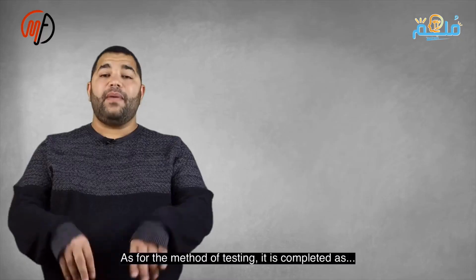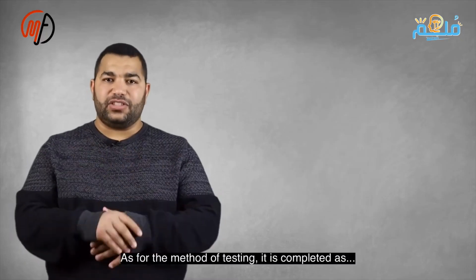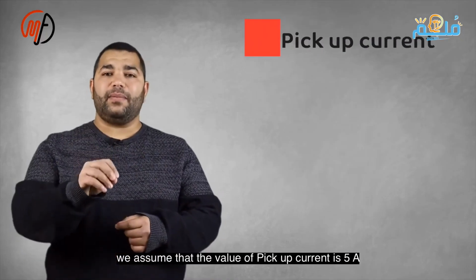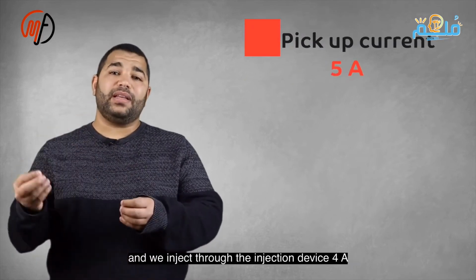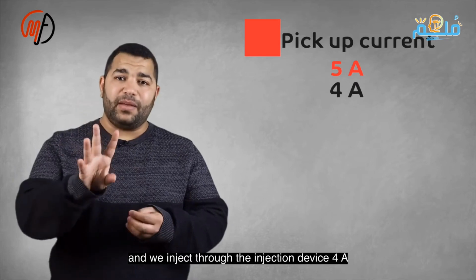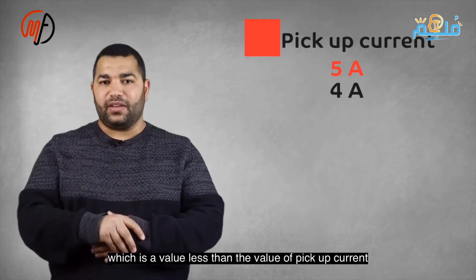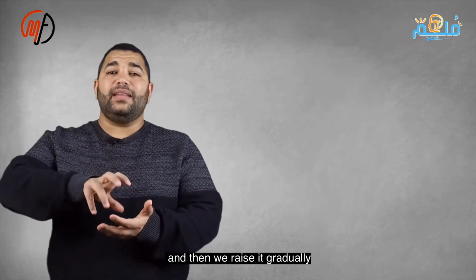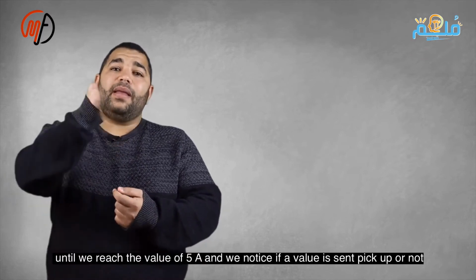Assume the pickup current value is 5 amperes. Inject 4 amperes with an injection device, below the pickup current. Increase to 5 amperes and check the relay for the pickup signal. Record the pickup current when the alarm appears. Decrease the current to record the drop-off current when the signal disappears.